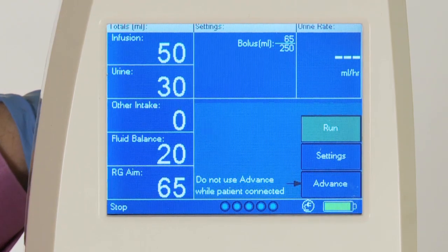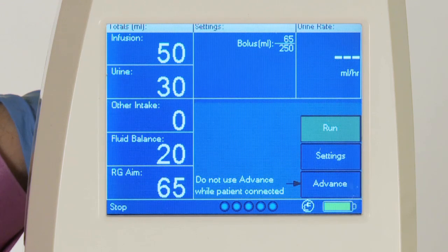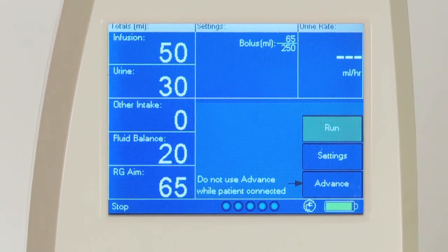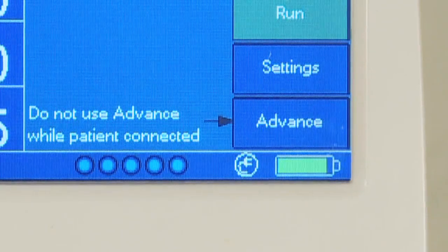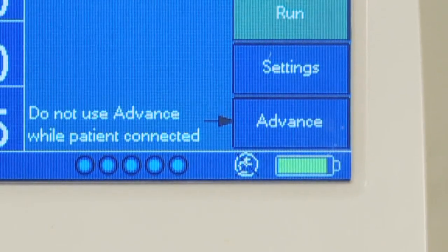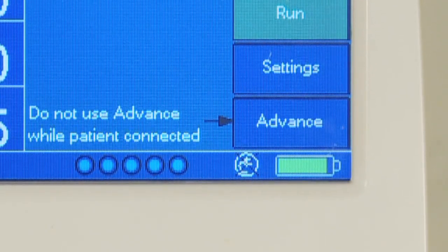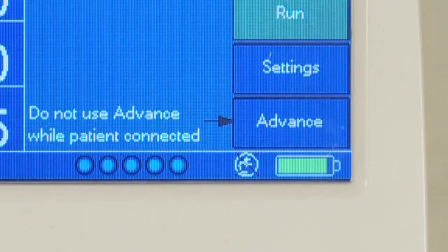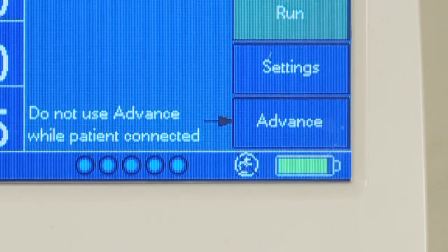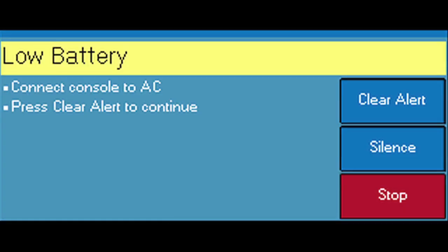RenalGuard has an integrated battery that should provide at least 30 minutes of operation unplugged. In many cases, a fully charged battery can last 3 hours or longer, depending on the pump speed. When the console is unplugged, the screen dims and the plug icon shows a line through it. The display in the bottom right of the screen provides an indication of remaining battery power. When an estimated 30 minutes of battery power remain, the low battery alert will be reported. When that occurs, plug in the console.